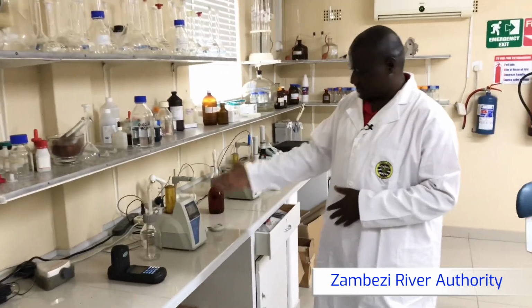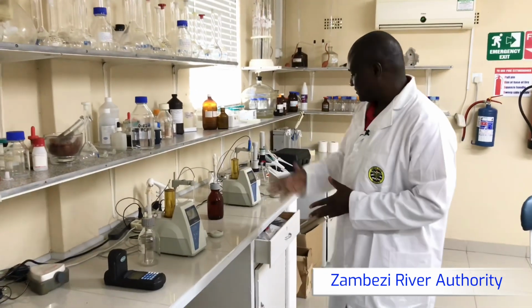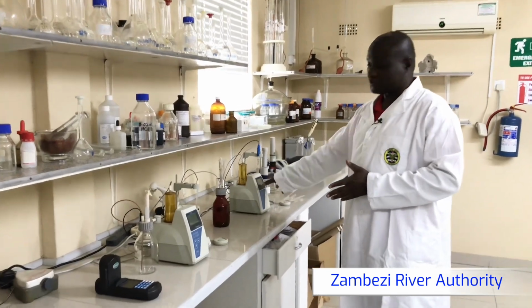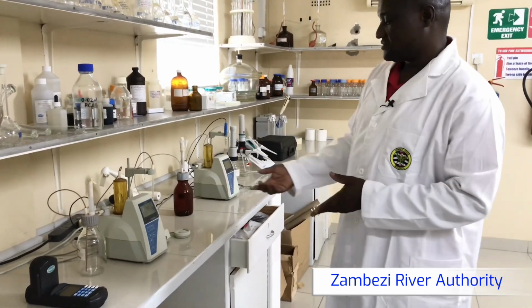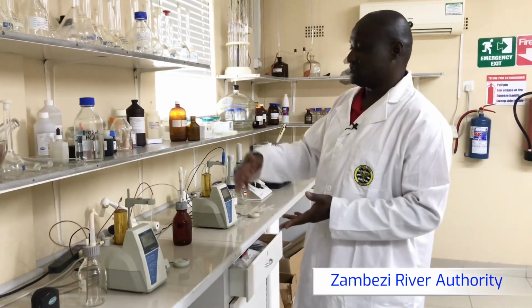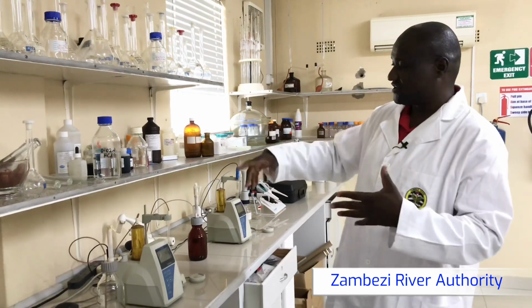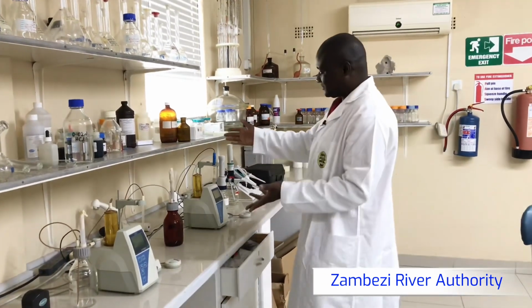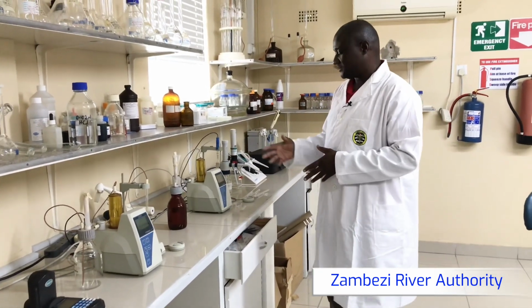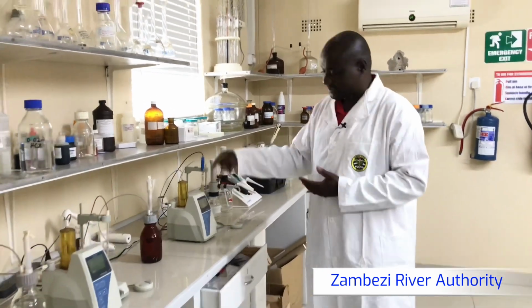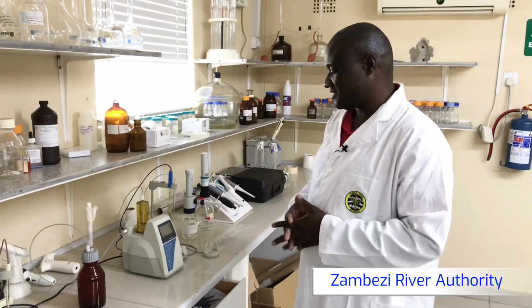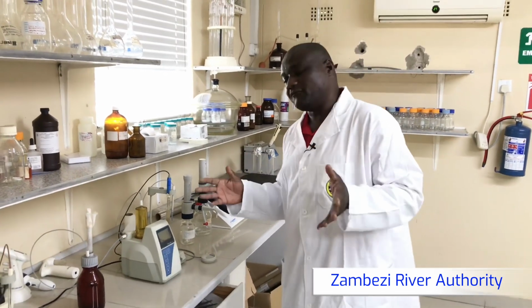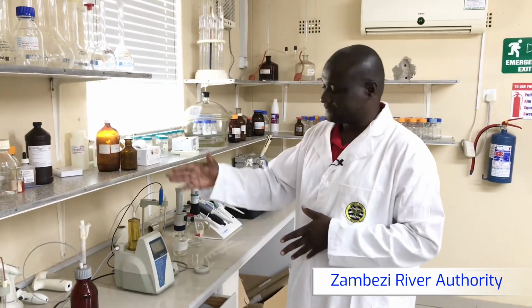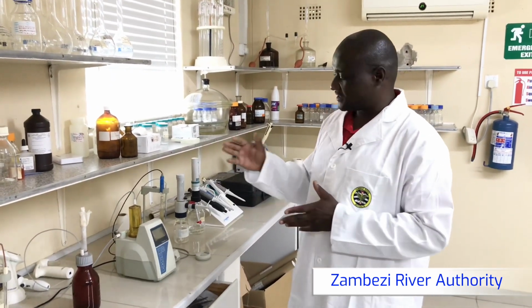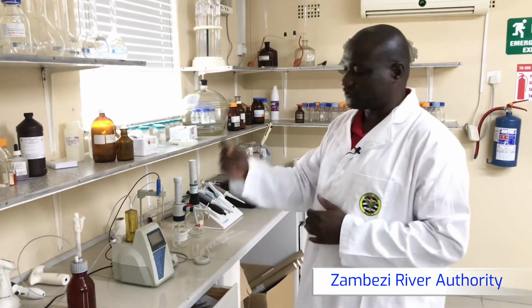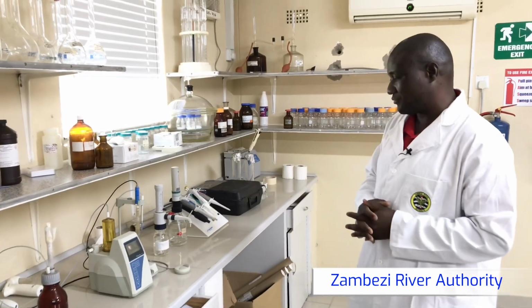Then what we have here is a titrator. It's a manual titrator. This is also a titrator, but this one is an auto titrator. With the manual titrator, the endpoint is determined visually, where your indicator changes color. But for this one, you program it in such a way that the endpoint will be determined by the probes that you put there. For instance, if you are doing things like total alkalinity, you can define your endpoint, say pH 4.5. So all you do is put your sample there, your titrant, and when it reaches 4.5, it will automatically stop, and it will give you the amount of titrant that has been used in that sample.